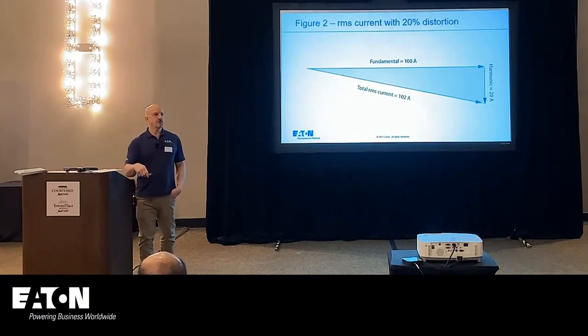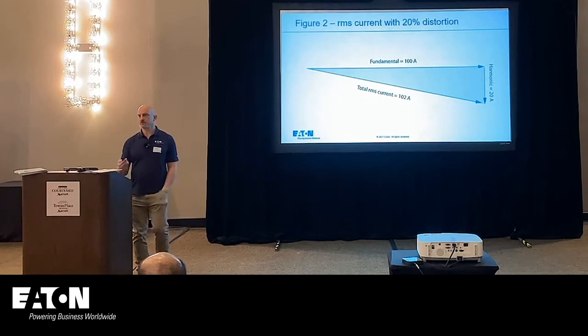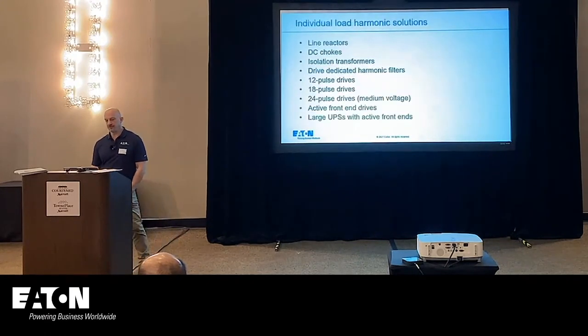Most of the issues with harmonics, if they're heating, it's excessive harmonic distortion. And again, it's self-inflicting. I'm usually screwing up my own system, so the utility doesn't really care about it. If it's above 20%, you start to get into some issues. But if you're designing a system that's above that, you have to really worry about what that is doing to my voltage. And that's really where the concerns come into play, where I'm screwing up my voltage enough to cause other issues.